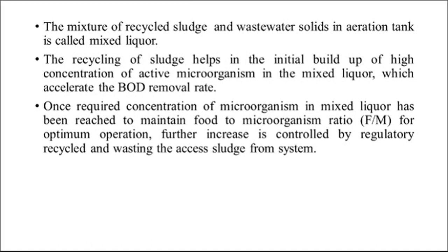The recycling of sludge helps in the initial build-up of a high concentration of active bacteria or microorganisms in the mixed liquor, which accelerates the BOD removal rate from the wastewater. Once the required concentration of microorganisms in the mixed liquor has been reached to maintain the food to microorganism ratio for optimum operation, further increase is controlled by regulating the recycle and wasting the excess sludge from the system.